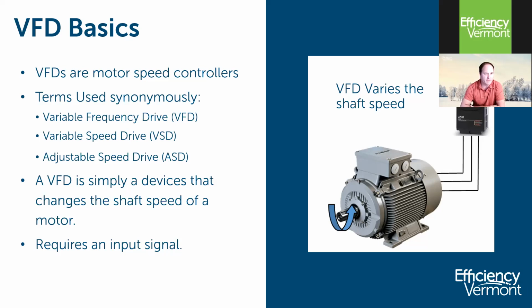Some synonymously used terms: VFD, VSD, ASD, they all mean the same thing. They simply change the shaft speed of a motor. They do require an input signal. There are some drives that can be done what's called set it and forget it, where you just turn it down to a fixed hertz speed. We have some pumps like that in the brew industry in Vermont, where the pump is a bit oversized, and so it's turned down to the point where they need the fixed flow, and it's left there. But that's a rare exception. In 99% of the cases, we are asking the drive to control the motor by way of pressure, flow, temperature. Those are probably the prevailing ones in HVAC, certainly. If there's not any questions, we'll move to the next slide.